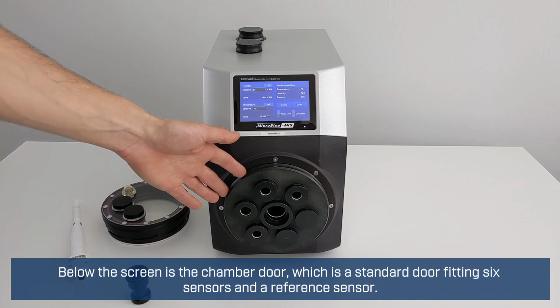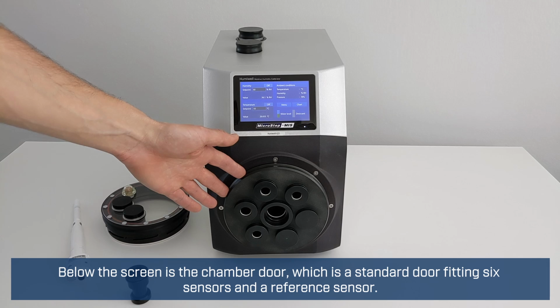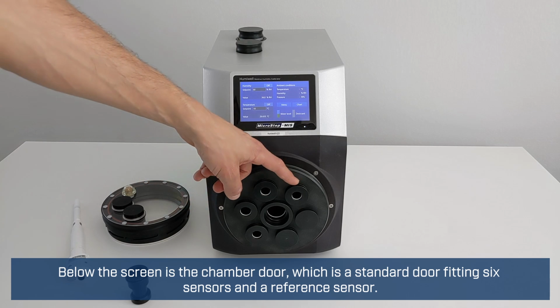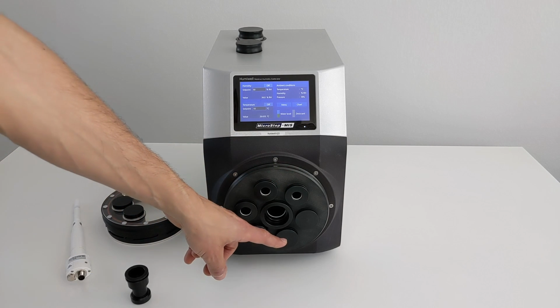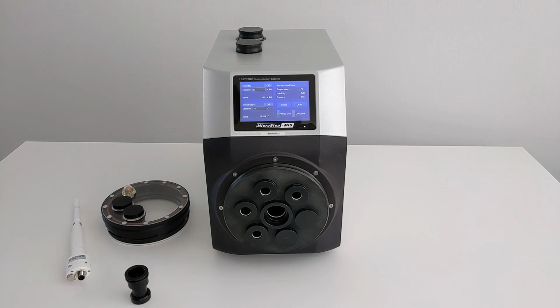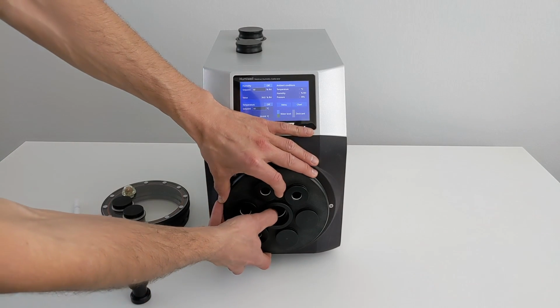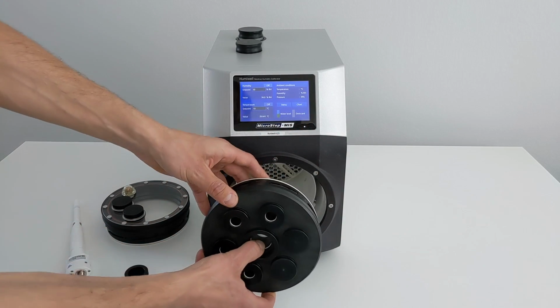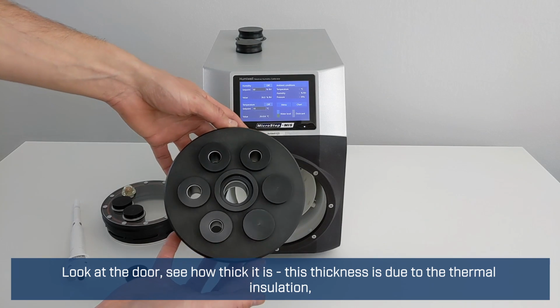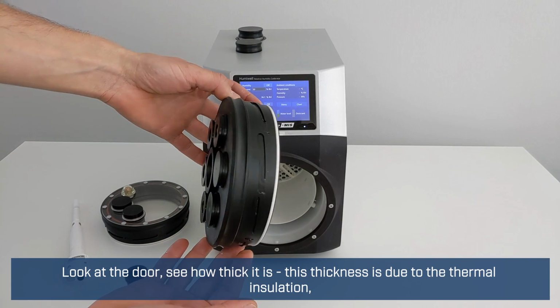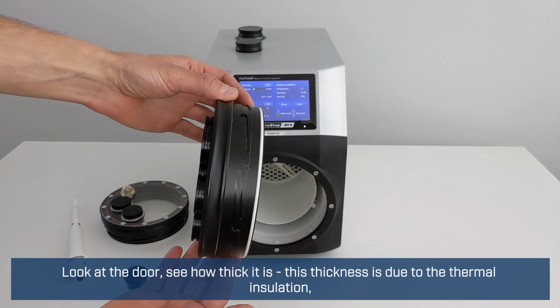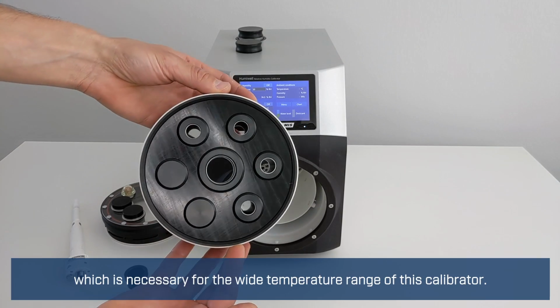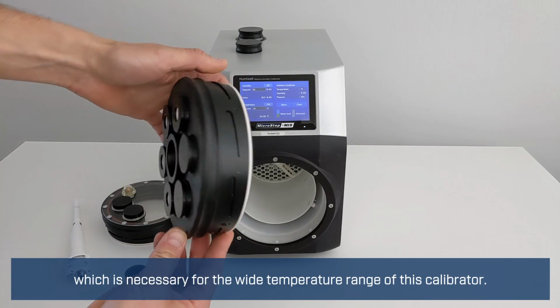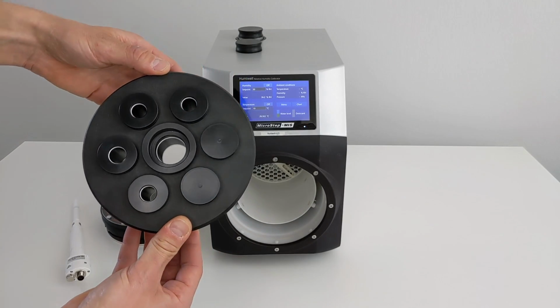Below the screen is the chamber door, which is a standard door fitting 6 sensors and a reference sensor. Look at the door, see how thick it is? This thickness is due to the thermal insulation, which is necessary for the wide temperature range of this calibrator.